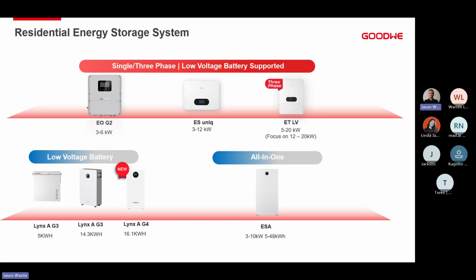On the left-hand side is our new EO G2 inverter. This is extremely new to the market for us at GoodWe. We've got a few units currently being beta tested in the SSA region, and the distributors will be starting to get stock of these hopefully very, very soon. From 3 to 6 kilowatts, this is our off-grid inverter. We can have it grid connected, obviously, to supplement the loads if PV is not high enough, or to charge the batteries. However, it is an off-grid inverter, so that's how we can use it.